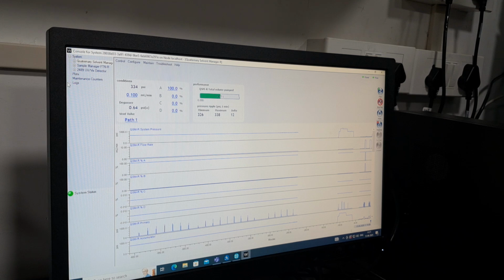Due to the communication failure it has been stopped, or it may be due to the flow, like sufficient mobile phase not being there. Sufficient mobile phase was there, so that is ruled out. Only because of the power supply. Apart from that, nothing.